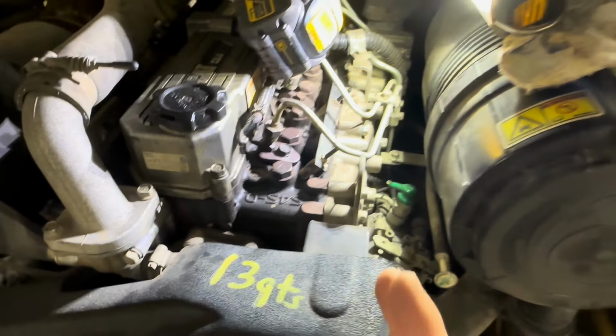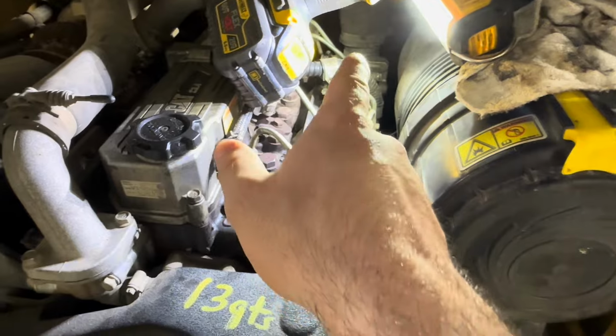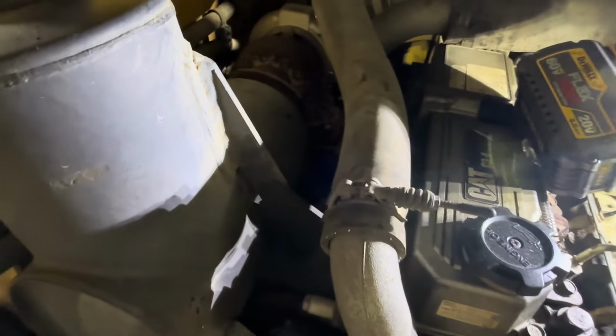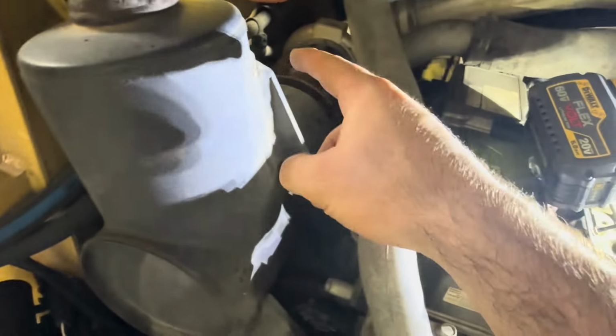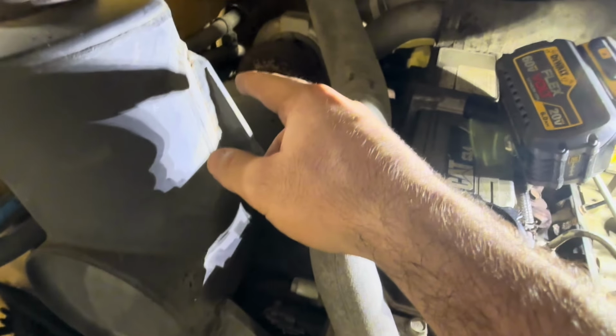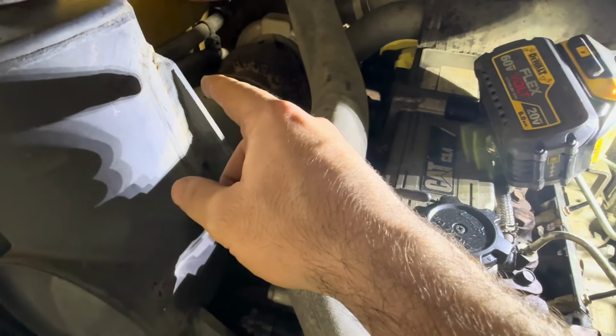So then I went and started tracing everything back. I followed that wire, did a continuity test, and that all checked out. I went over to that cold start relay, swapped it out for a spare that I had. That didn't make any change.